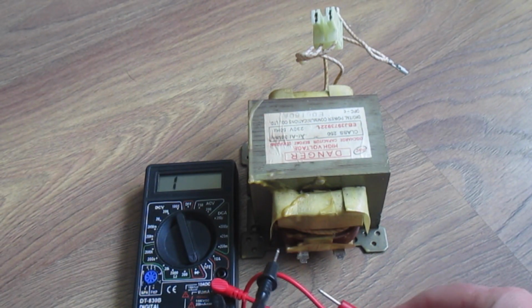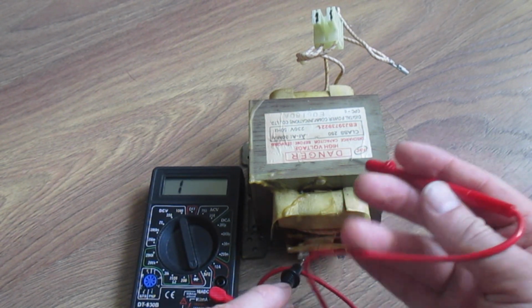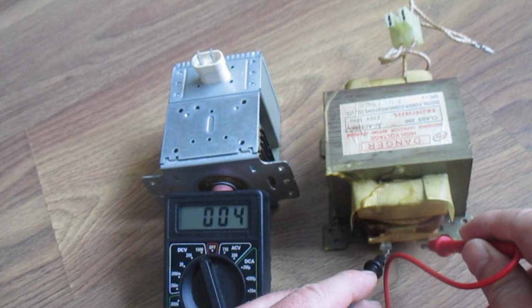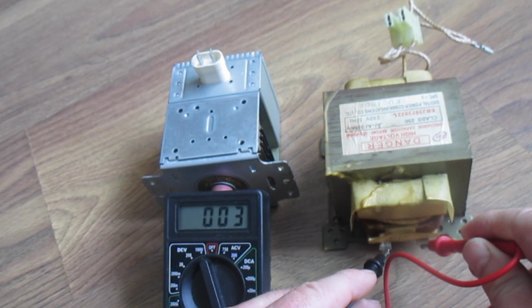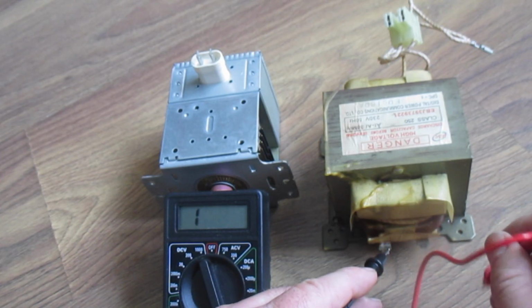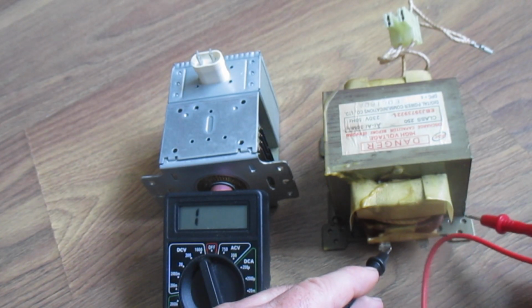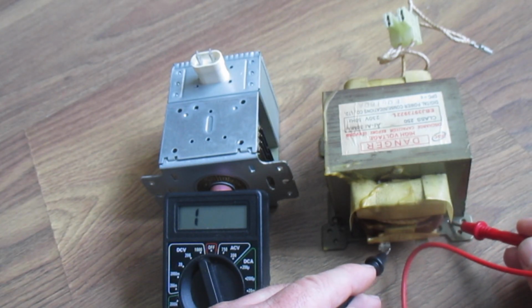Next, I check the transformer and the primary winding and set the multimeter to continuity mode. I'm checking these two contacts. They ring, which is good. Now I'm checking each contact for breakdown to the case. There's no breakdown, which is excellent.